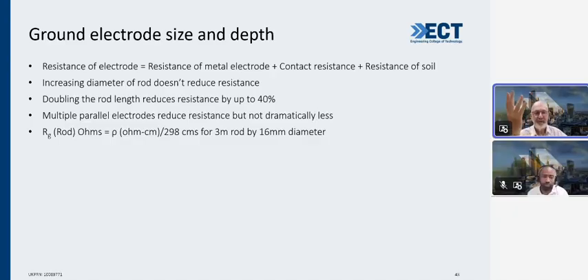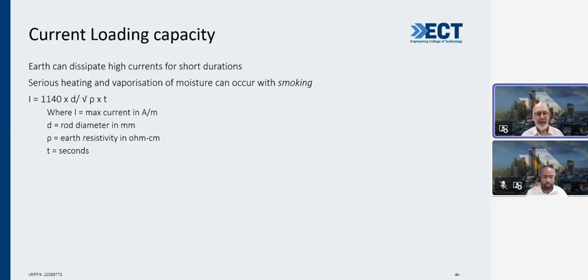The resistance of the electrode is the resistance of the metal, the copper, the contact resistance, and then the resistance of the soil, the resistivity. One of the funny things which people find quite surprising is that when you put the rod into the ground and increase the size of the rod, it doesn't really have much impact. It's actually the depth of the rod in the ground. So increasing the diameter of the rod doesn't reduce resistance. That's not quite correct: it does, but it's not a big impact. Doubling the length of the rod reduces the resistance quite significantly, and obviously you can put multiple rods in parallel. Earth can dissipate high currents for short durations. Obviously, you could have serious heating and vaporization effects as well, smoking, and there's a calculation on the smoking current there.